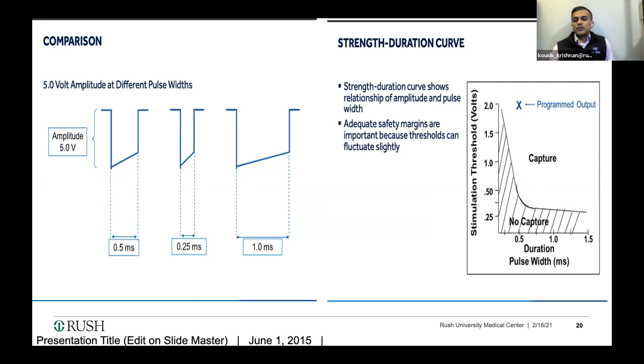And then we can also create a safety margin, because we don't want to pace the cardiac muscle at exactly the amount that can lead to capture, because there could be electrolyte changes. The lead, at least initially, could move a little bit, and you want to have a safety margin so that you don't lose capture.